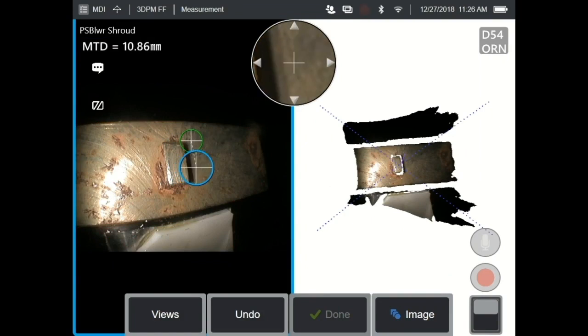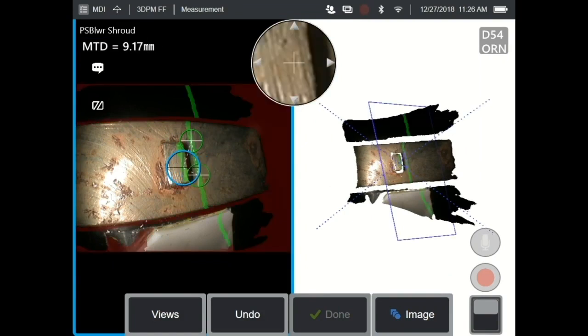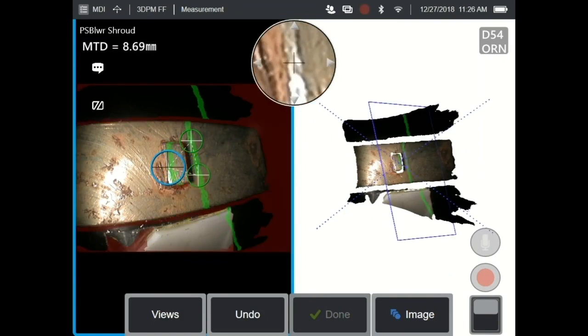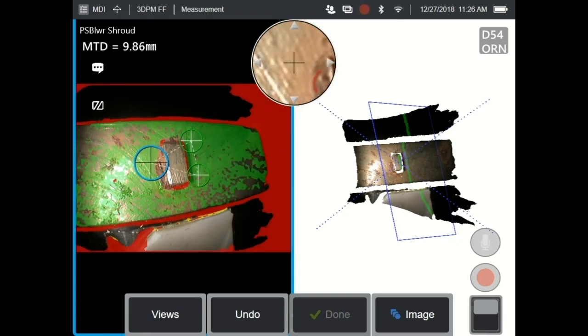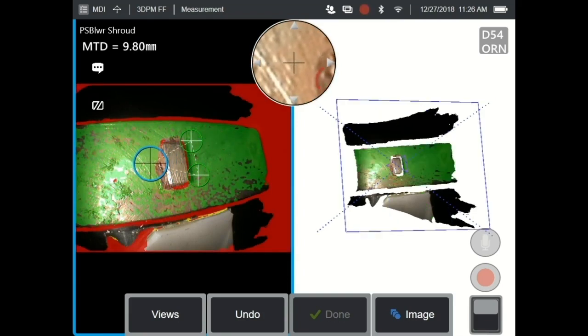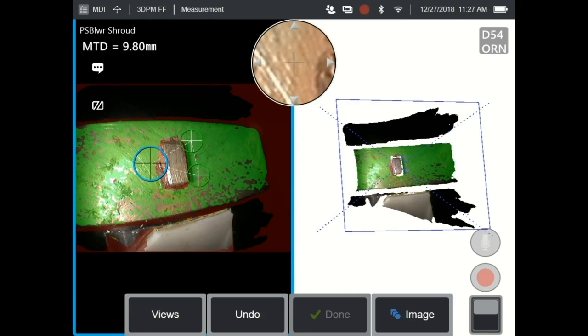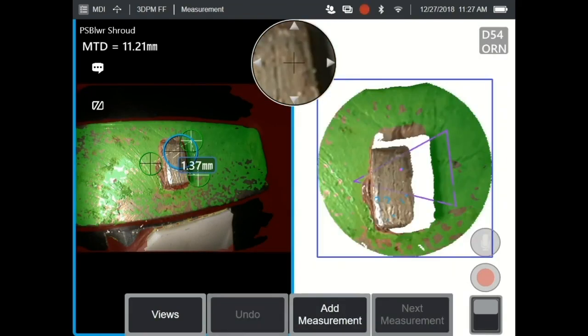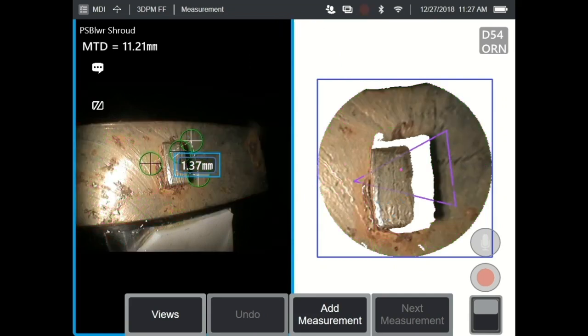My green surface mask is telling me that I'm on a fairly flat surface surrounding that indication, and that I'm getting 1.37 millimeters, or if I touch that, so let me cycle through to make it active, get it out of the measurement area, touch it for about a second and a half, and you see that I'm now getting 54 thousandths of an inch.